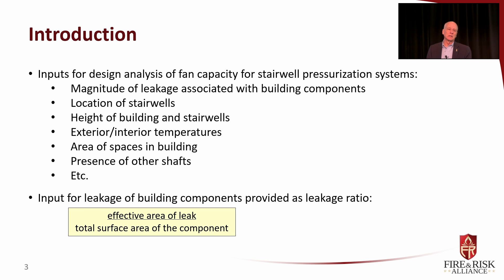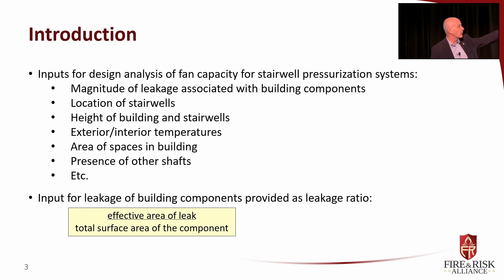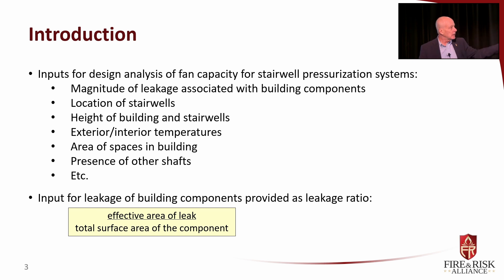One of the keys is the magnitude of leakage. The fan capacities we get for stair pressurization systems are pretty sensitive to the leakage characteristics of the building, as you might intuitively expect. The input for leakage of building components is provided as a leakage ratio — what's the effective area of the leak? We account for all the leaks of that exterior wall, including windows that are not airtight, and divide that area by the total surface area of that component to get a ratio: how leaky is that wall?